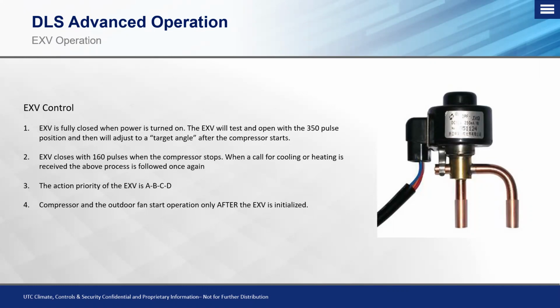So the action priority of the EXV is A, B, C, and D. And of course, those are all going to be your individual zones. That is the same reason that we tell you, depending on what kind of multi-zone system you have, that your largest tonnage needs to start at port A and then work its way up, B, C, and D. For example, if you had a 2-ton indoor unit, the 2-ton should go on port A. If you had two 12,000s, they should go on ports B and C, and then the 9,000 would go on D. So start from the bottom, work your way up.